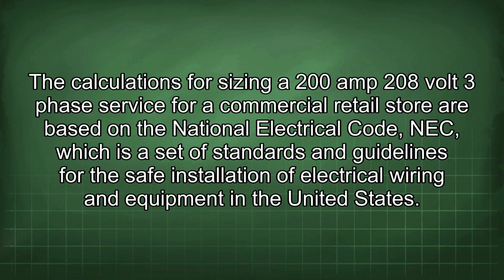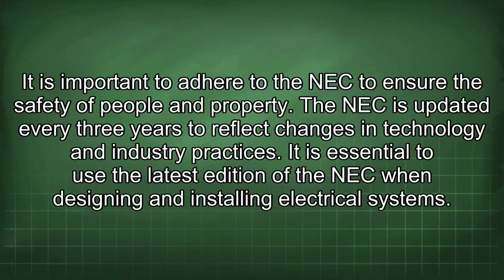The calculations for sizing a 200 amp 208 volt 3-phase service for a commercial retail store are based on the National Electrical Code, NEC, which is a set of standards and guidelines for the safe installation of electrical wiring and equipment in the United States. It is important to adhere to the NEC to ensure the safety of people and property. The NEC is updated every 3 years to reflect changes in technology and industry practices. It is essential to use the latest edition of the NEC when designing and installing electrical systems.